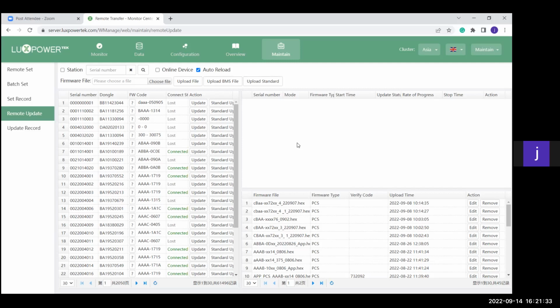So it's very important to switch over the inverter to the grid, meaning your whole house must run on Eskom while you're updating the inverter. So you should install a changeover switch so that you can decide whether the inverter or Eskom is supplying all the loads in the house, because the inverter will restart 2 to 3 times depending on which update is running on this inverter. And every time it restarts, your Wi-Fi will go off, your fridges will go on and off, and it's not good for all the appliances in the house. So you just flip the changeover switch so everything stays on in the house while the inverter is updating, and the updating will go much faster and smoother once one is doing this.